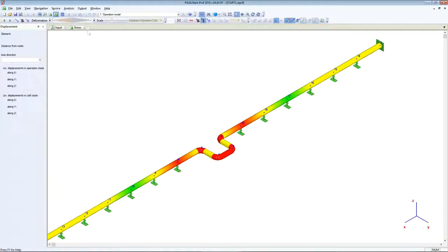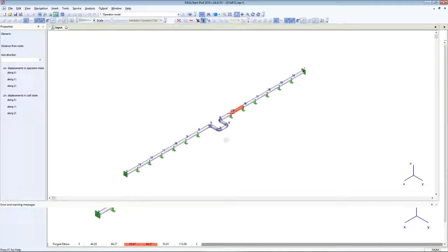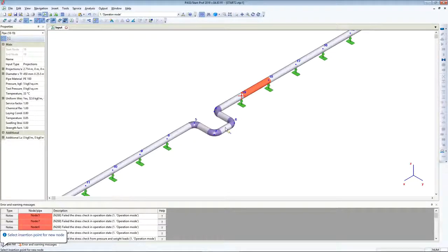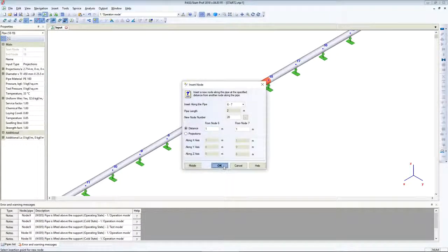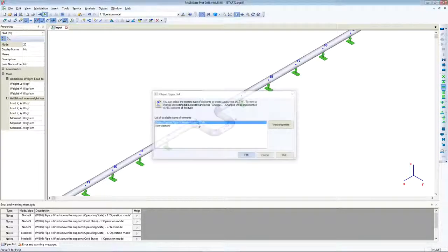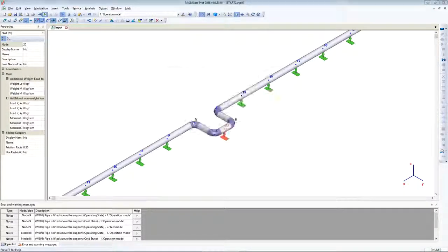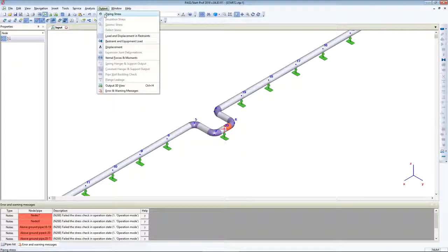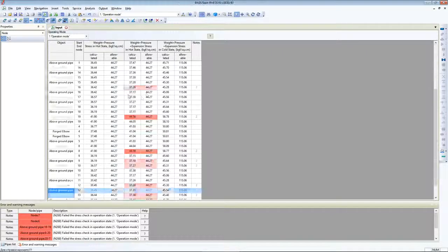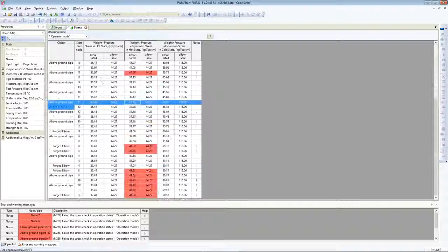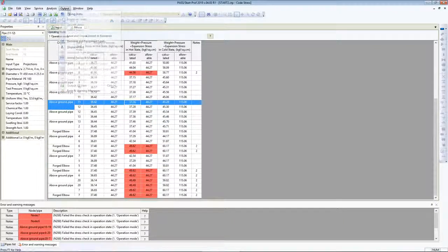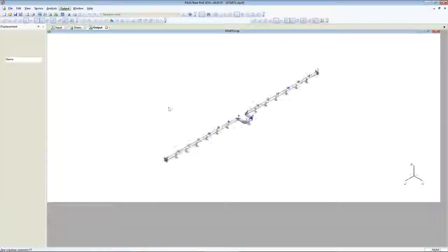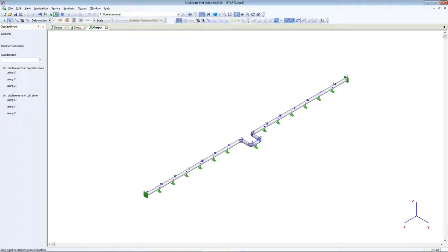Let's return back into input data and add additional supports here. I will add just one support and run analysis again. Now I see that all weight loads are OK. We have no problem with weight loads anymore.